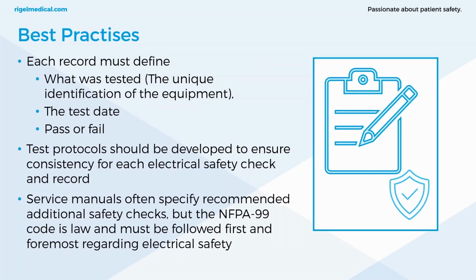NFPA 99 states the minimum documentation that's required for routine checks. Each record must at least define these things. Now, you might actually record more than this, but this is the bare minimum. What was tested, that's the unique identification of the equipment, the date it was tested, and whether it passed or failed. Test protocols should be developed to ensure consistency for each electrical safety check and record.